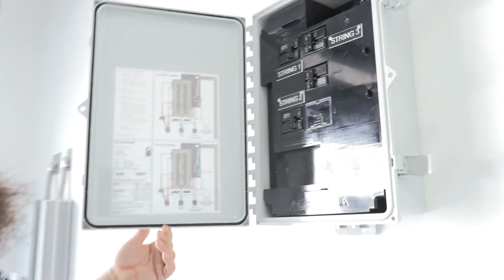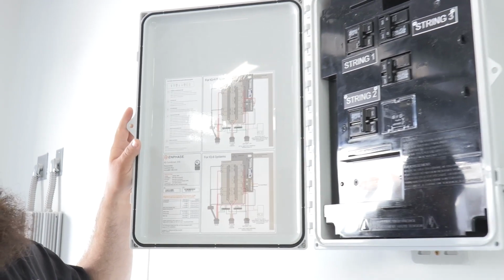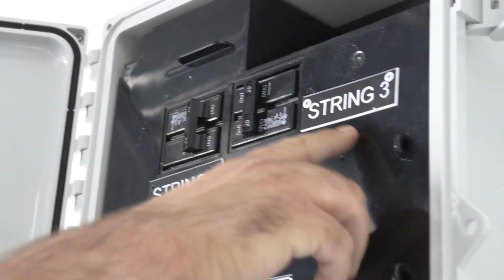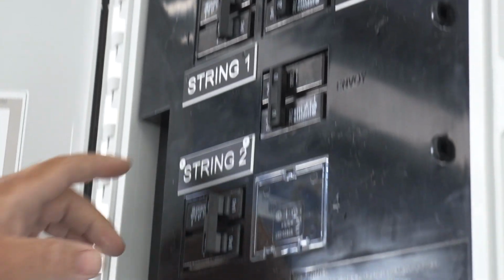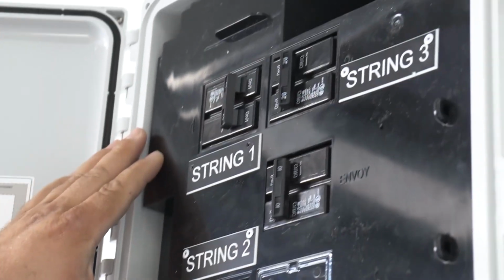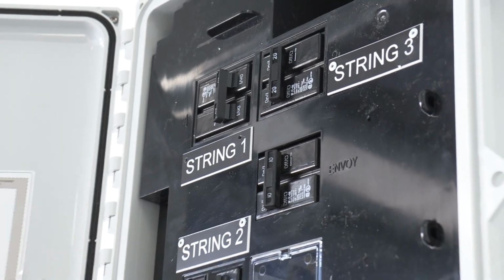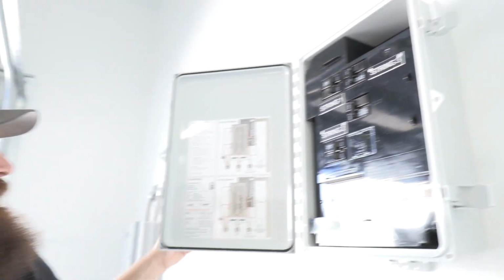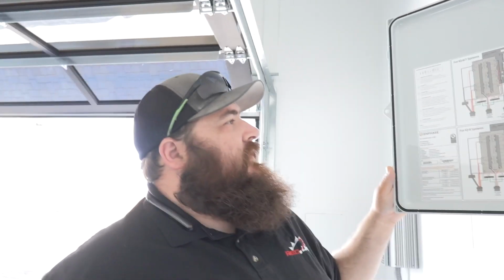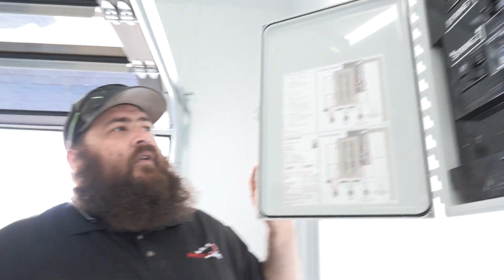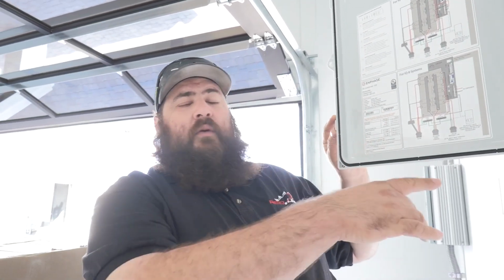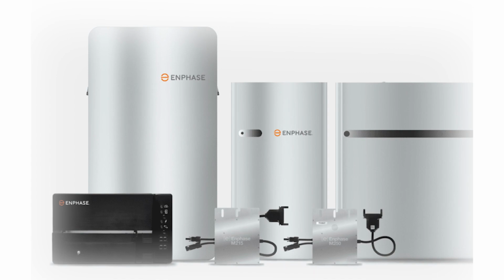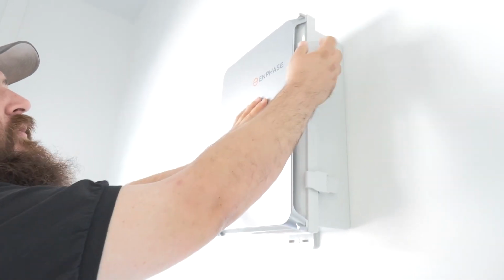This is our smart switch. We have so many panels on here, we have multiple strings of panels. They use the microinverters, but this is where we actually bring them all together. As you can see, we have 3 different strings on here. We bring them together, and then this unit is what actually feeds into the panel. It's our combiner box. All of our roof solar comes to here before going to what we saw on the other side and going into our electrical panel through the meter and disconnects. Enphase has a lot of good products that we like to use to match to your house.